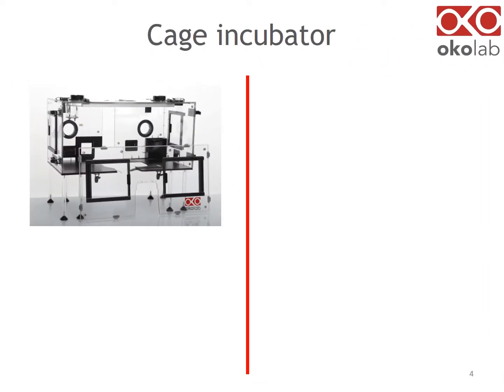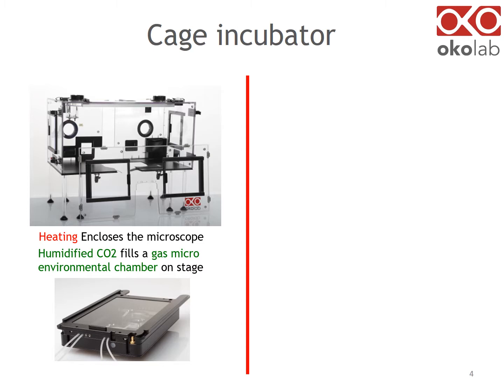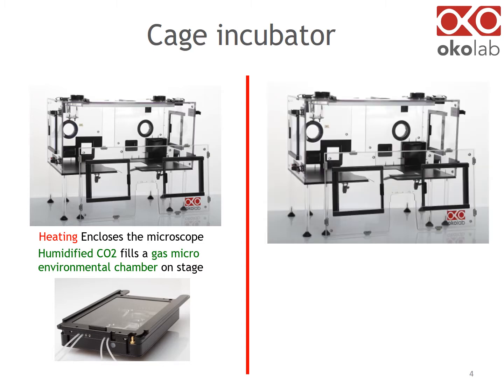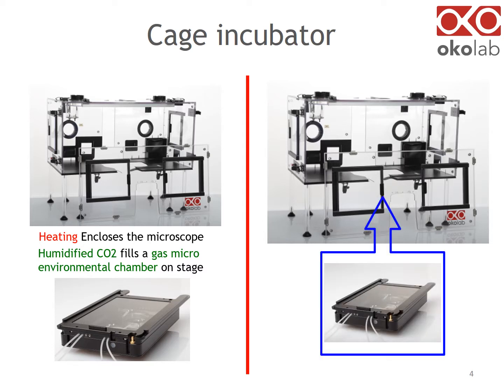In a cage incubation system, heating encloses the microscope. The stage, objective, and nose piece are located inside the enclosure at 37 degrees. The system is complete with a microenvironmental chamber preventing humidified CO2 from dissipating. You will place your sample inside this chamber and locate it on the stage, in the enclosure, at 37 degrees. The enclosure provides an extremely stable environment, protecting your sample from drafts due to air conditioning cycles or foot traffic in the microscope room.